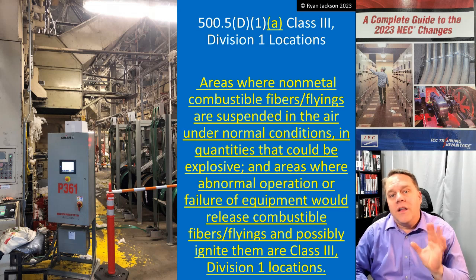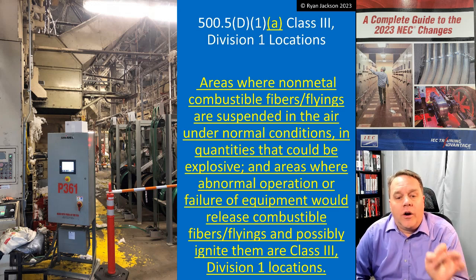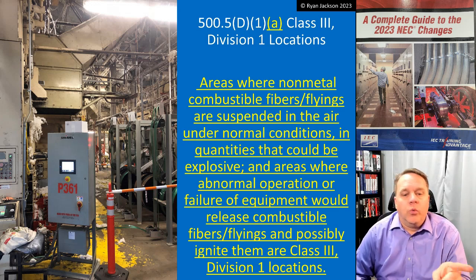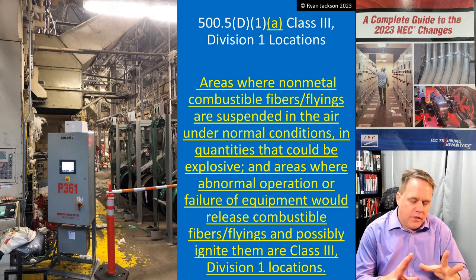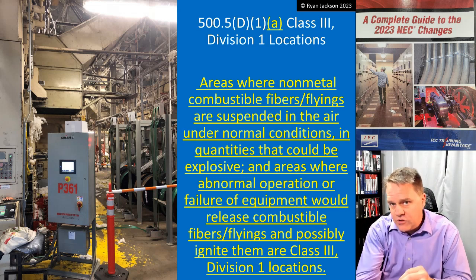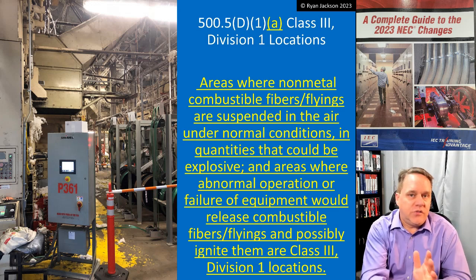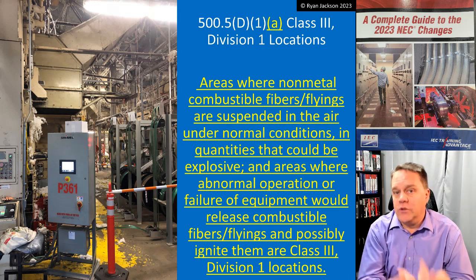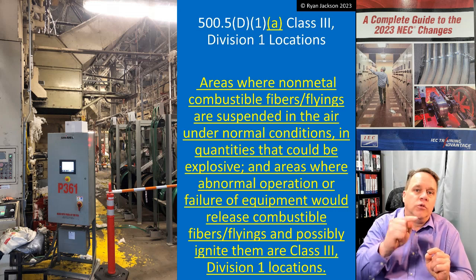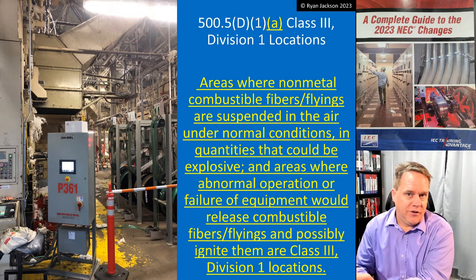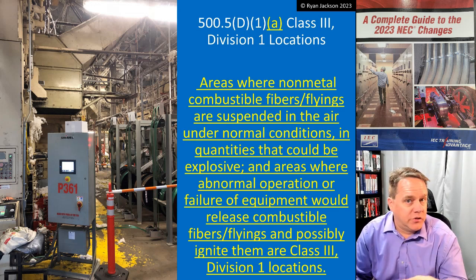We're also going to classify any area where abnormal operation or failure of equipment would both release fibers and flyings and ignite them. It's not enough that equipment breaking down would just release the ignitable or combustible fiber flying — if abnormal operation only releases the material, that's usually Division 2. If abnormal operation both releases and ignites the material, that's Division 1.